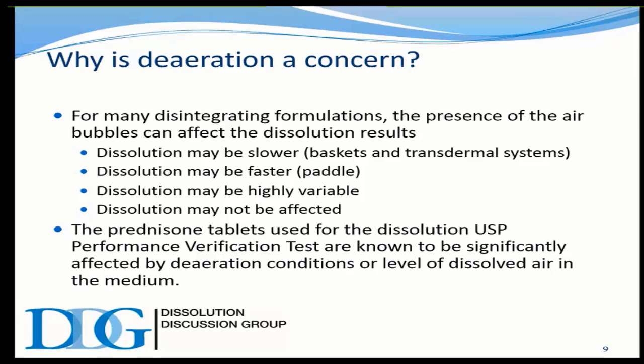But mainly it's variable, and it's maybe not as much position to position with the dissolution apparatus, but from test to test. Even aeration levels from purified water sources during the day in laboratories can be quite variable. And we're going to discuss the modern ways that most purified water is made and the impact that this has on dissolution. And then again, there are products that are just unaffected by dissolved gases. If they're present or not, the results are the same. So in those cases, deaeration is not required because you've proven that it is not an interference to the test.